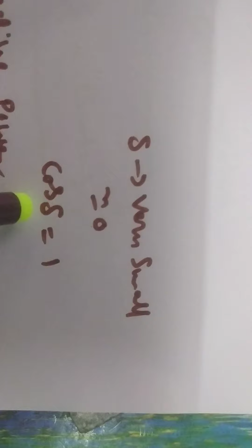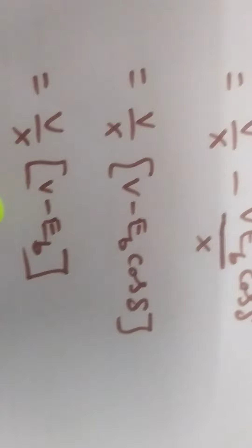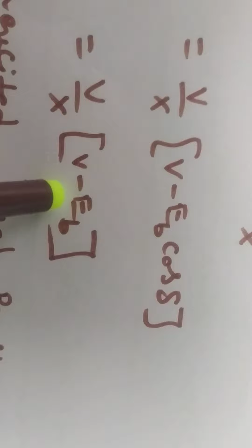Generally this synchronous machine is designed for providing reactive power compensation, but it is not taking any mechanical load. It consumes only a small amount of no load losses, which is negligible. Delta is approximately 0, and hence cos delta is equal to 1. Therefore the equation reduces to V by X into V minus EB, where V minus EB is the difference between bus voltage and induced voltage.